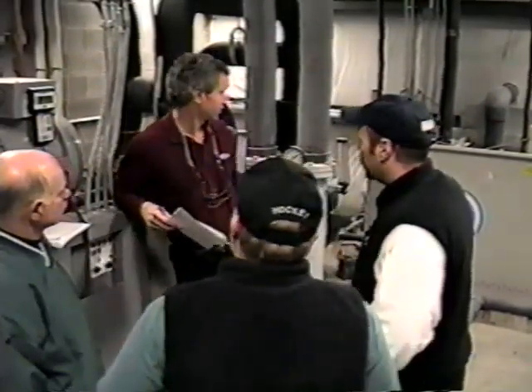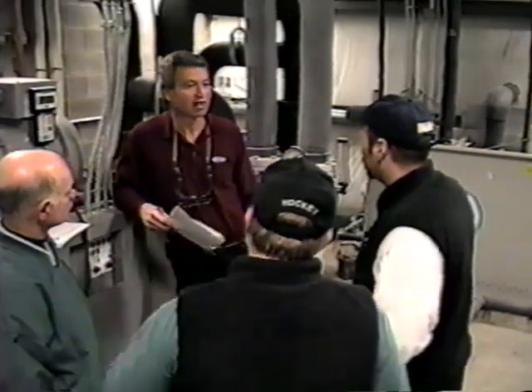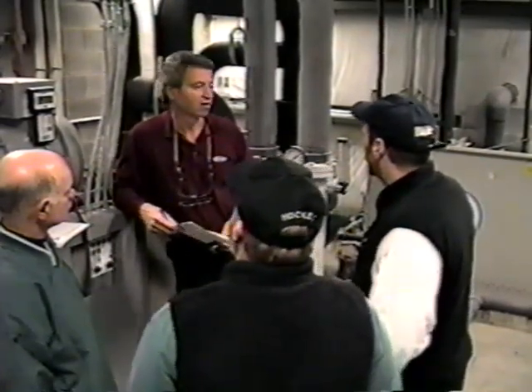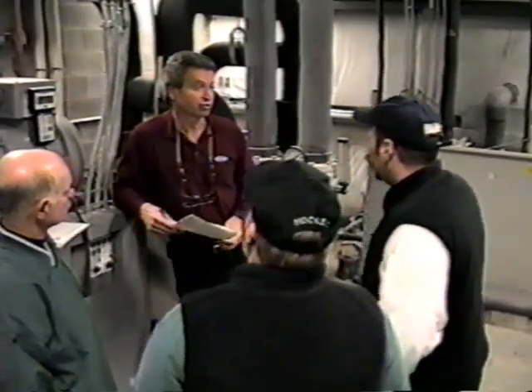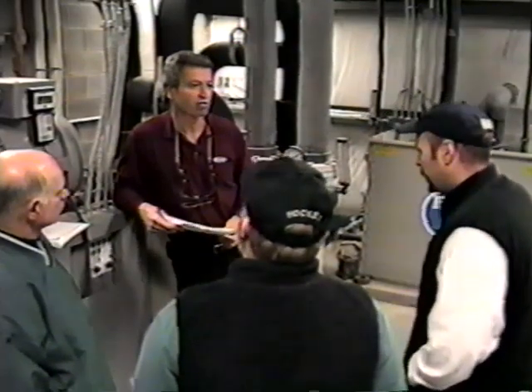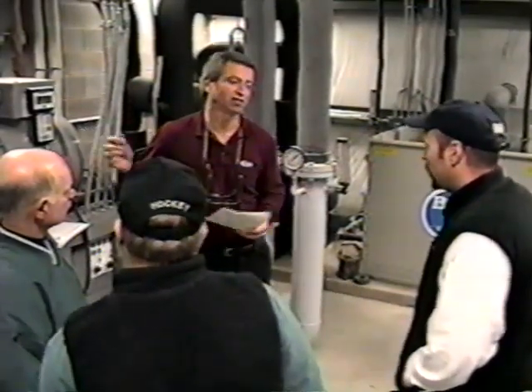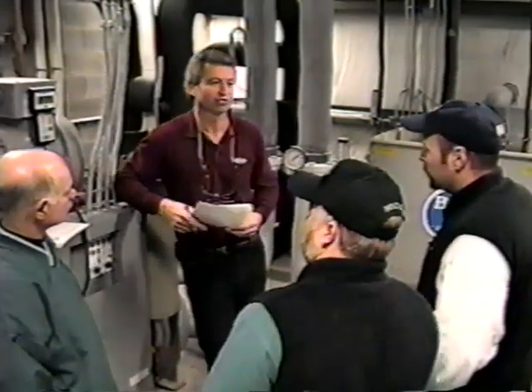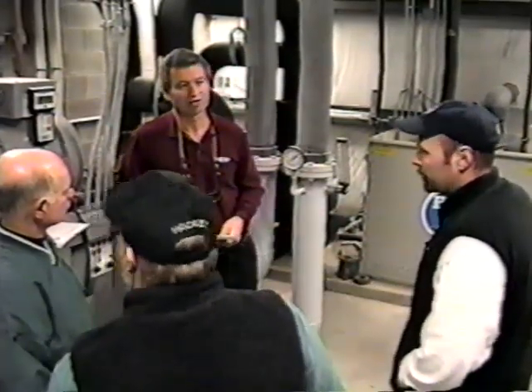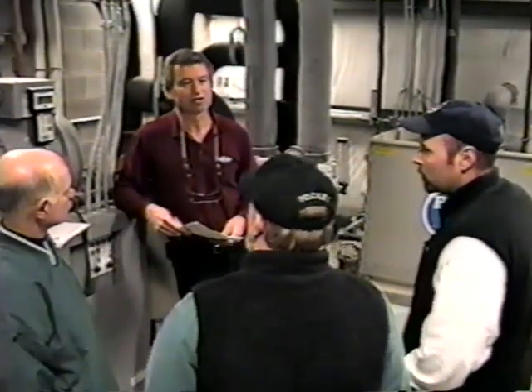And then probably the first thing to do is start feeling your pipe, see if you've got hot water or something. Either your pump shut down or your tower's a problem. So again, this is going to lead you to an area to start looking closer. It's not going to tell you exactly what the cause is, but it's certainly going to lead you in the right direction.